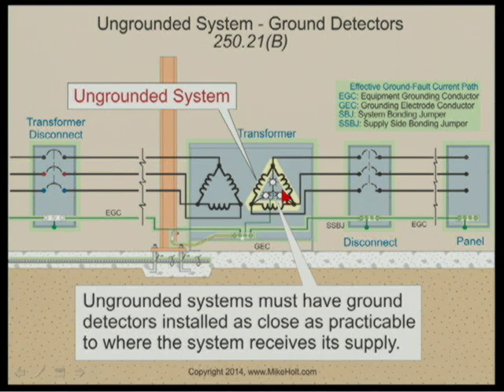The secondary is going to be at that voltage. Would I have any light bulb working here? Would a light be lighting up here? On the normal condition? Normal conditions, yes. That's right, because we're going from this one phase through the light bulb going inside here. So the lights would all be on, somewhat dim, as long as there's not a ground fault.